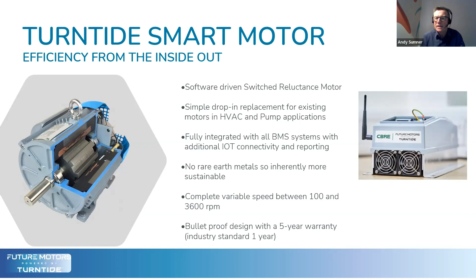Very quickly on the motor itself, it was explained very much in the video. A couple of really important takeaways: first, it's a very simple proposition. You simply replace the existing motor with our motors, hook it up to the existing fan and propulsion system, and away you go. It's fully BMS agnostic, so we'll integrate with all BMS systems - BACnet, Modbus, 0 to 10, 0 to 1000 millivolt - and it's completely variable speed.